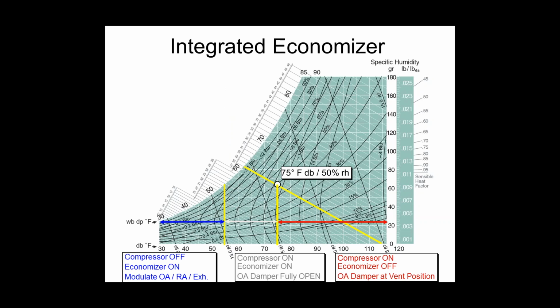If you have an integrated economizer, our psychrometric chart looks a little bit different, right? So the blue area on the left, below 55 degrees, I can get it all done with free cooling, right? If I'm trying to get 55-degree discharge air and I've got 55-degree outside air available, I should be able to get it done. Maybe a couple degrees for fan heat, but conceptually I've got to get it done. If it's really warm, 75 degrees outside and above, I'm probably going to have to run compressors and shut the economizer off. And if I'm in that middle area where the white arrows are, between 55 and 75, I'm probably going to be in integrated economizer mode, which means I'm trying to do it with the outside air damper, but if that's not cutting it, then I'll engage the first stage of compression to help me out.